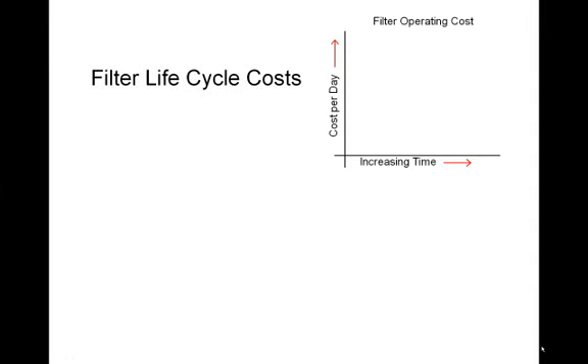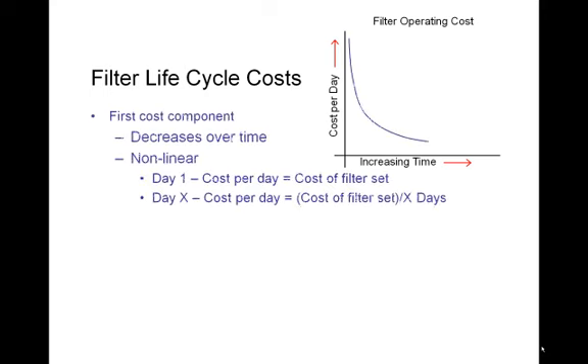The life cycle cost of a filter — if you look at the cost per day versus time, there's a first cost component that decreases over time, and it's very non-linear. Say you spend $1,000 for a set of filters for an air handling unit. The first day you run those filters, it costs you $1,000 a day. The second day, $500. The fourth day, $250. So you have this exponential decay in cost over time.